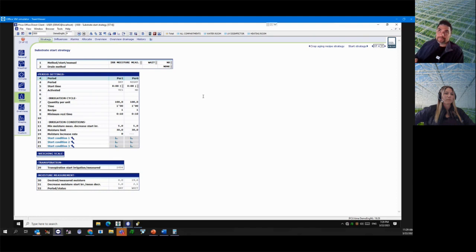Grodan do sell them. It might depend on the model, but they do have their own SDI-12 converters, which you wire the sensor to. From those converters, it changes the SDI-12 to a standard 0 to 5 volt signal, and then we can pick it up. But if they do not have an SDI-12 converter, then you will need SDI-12 converters directly from us. So it will be an equipment cost and software to do the conversion from SDI-12 to a standard one. But yes, it is possible. Thank you. Yeah, no problem.